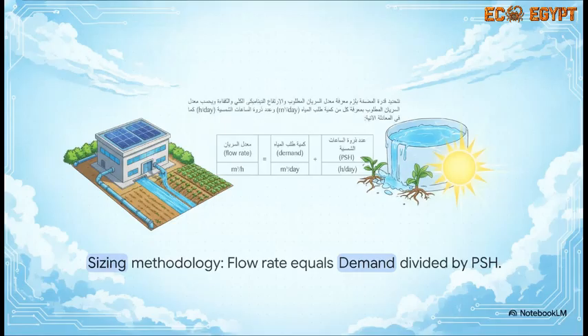So, the crucial point is, how do engineers actually size these stations? Well, it all comes down to a really vital formula pulled straight from the source material. Your required flow rate, which is measured in cubic meters per hour, equals the total volume of water demanded by the crops per day, divided by the site's peak sun hours, or PSH. Notice it's not total daylight hours. You size strictly on those specific hours of peak solar irradiance. That guarantees the pump moves enough water while the sun is at its absolute strongest.